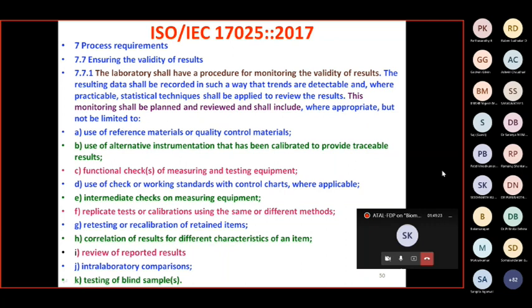Okay, so what are the checks or monitoring you do? One is use of reference materials or quality control materials, whether it has been done properly. Use of alternative instrumentation that has been calibrated to provide a traceable result. Functional checks of measuring and testing equipment. Use of check or working standards with control charts wherever applicable. Intermediate checks of measuring equipment as envisaged in the equipment suppliers' manuals. Replicate test or calibration using the same or different method, to provide reliability or repeatability assurance to the customer. Retesting or recalibration of retained items, to ensure whatever results we have given to the customer are valid. You will do one more internal test by yourself later.